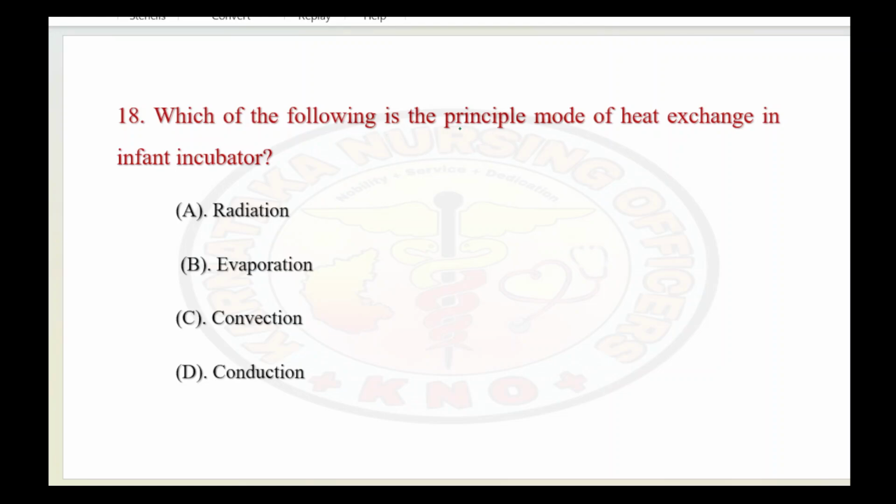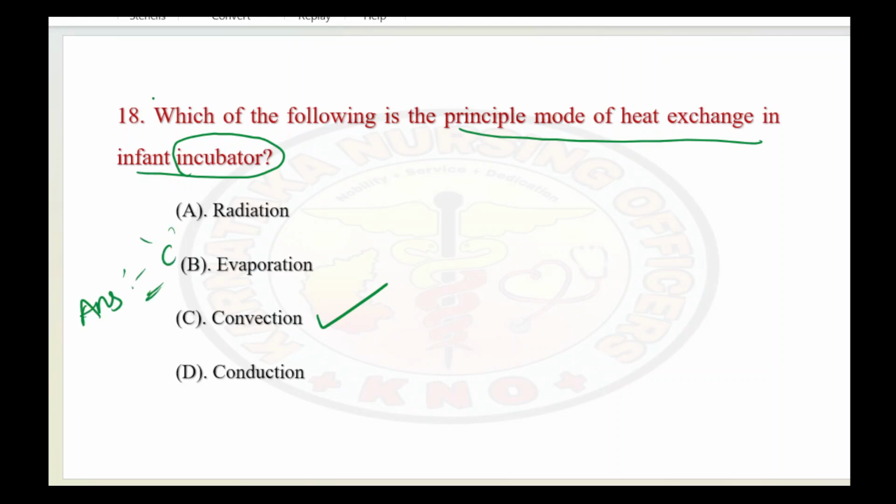Which of the following is the principal mode of heat exchange in an infant incubator? They have asked you only about the incubator, not about the remaining aspects. So in the incubator, the right answer is convection. I'll tell you why it is convection.